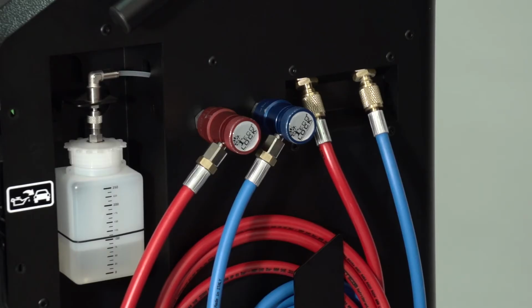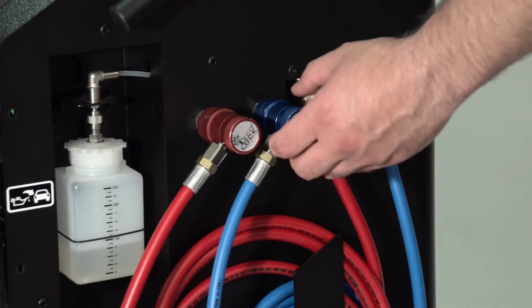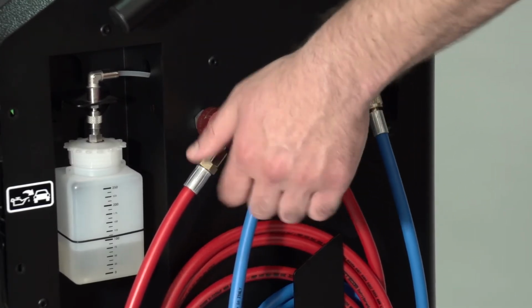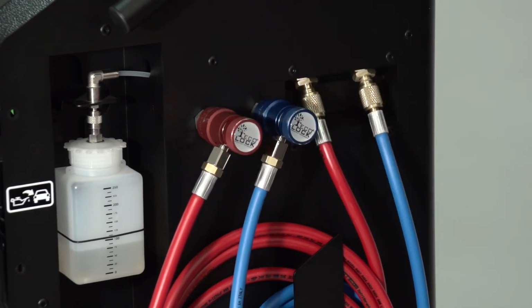At the end of the service, it'll prompt you to close the couplers. Close the couplers. EcoLock process will start once you press continue, and it will evacuate that little area again before it allows you to disconnect. It's important that you follow the prompts on the machine with this enabled. With EcoLock enabled, it is a roughly 3 minute process each time, so it adds about 6 minutes to the entire service. And EcoLock can be disabled in the settings if they choose to.